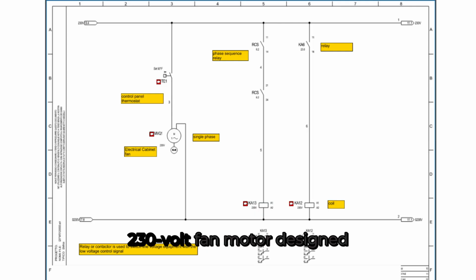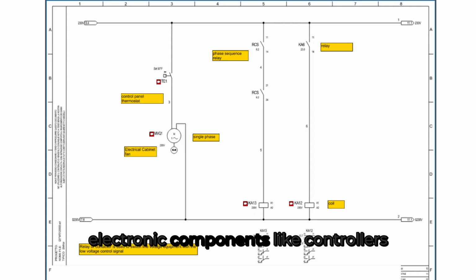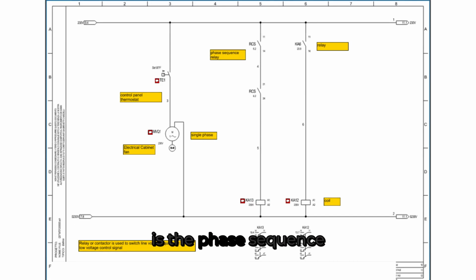This is a single-phase 230 volt fan motor designed to maintain airflow within the control panel and prevent overheating of sensitive electronic components like controllers and relays. The next component shown is the phase sequence relay, labeled RC5, downstream from the phase monitor. The control power continues to two relays labeled KA13 and KA12. Both are 230 volt AC coil relays, used to switch or interlock other parts of the control circuit. Each relay includes its own normally open (NO) and normally closed (NC) contacts, which can control different control signals or interlocks as needed. Their coil terminals, A1 and A2, are clearly shown here, indicating that both operate from the same 230V control supply. At the bottom of the diagram, we can see the relay contact diagrams for KA13 and KA12, showing how these relays control other control loops in the system.